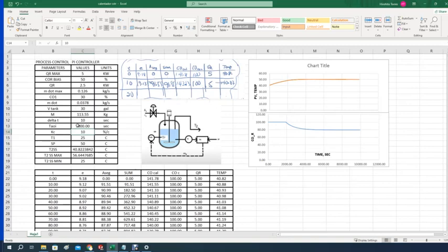That's basically it. So a combination of tau I of 3,000 and a Kc of 10 provides a pretty good and decent behavior for the PV to reach the desired temperature. Again, you can increase Kc and tailor tau I to behave accordingly. Again, there's a technique to get the optimum values for tau I and Kc, and that's what the third video is about, because that's open loop. If you do an analysis of the open-loop behavior of this vessel, you might come out with the proper Kc and tau I values as required for this system. When you have that, then you can keep tuning.